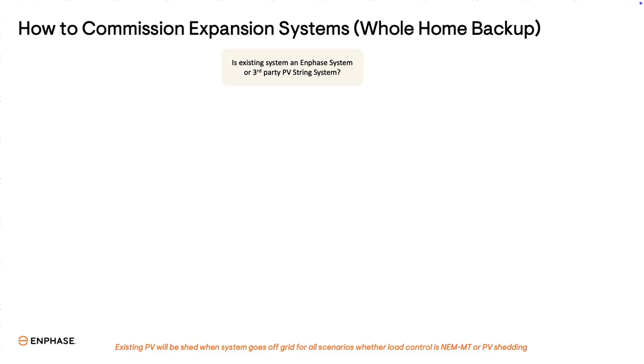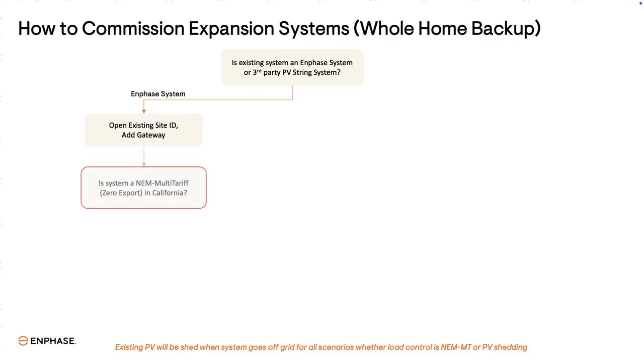The commissioning flow for expansion systems with batteries varies depending on whether the system has backup capabilities or is grid-tied without backup. This decision tree shows the commissioning flow for whole-home backup expansion systems. First, determine if the existing system is an Enphase system or a third-party system. If it's an Enphase system, open the existing Site ID in the installer app and add a gateway. Then determine if it's a NEM multi-tariff system in California. If yes, set load control to NEM MT. If no, set load control to PV shedding. The NEM multi-tariff and load control settings are critical to the proper operation of the system and compliance with the NEM multi-tariff rules of California utility companies.